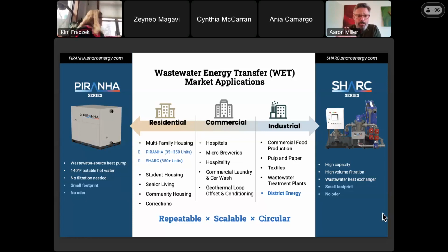On the right side, the SHARC is, to get down to it, a specialized heat exchanger with a wide gap plate and frame that allows us to run sludge through it. On the front end, we've got a specialized filter that removes enough of the large solids so we can move that wastewater through the heat exchanger and do our thermal transfer without everything jamming up. In 15-plus years of operation, we've never once had to open up a machine for jamming.